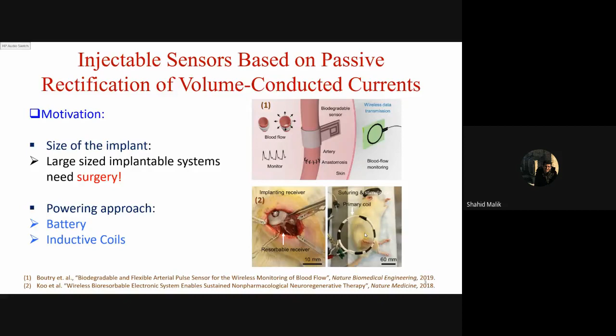So what we are proposing is to use body tissue, because tissue in the body is conductive, so it can carry the power to the implant. So rather than using some inductive form of power transfer and batteries, we can just directly use body tissue as a conductive medium to transfer power from outside to the implantable device. In this case, we need neither a battery nor a coil. So we can reduce the size of the implant to only the electronics part and the sensor part. This can lead to a very miniaturized implant for medical purposes.